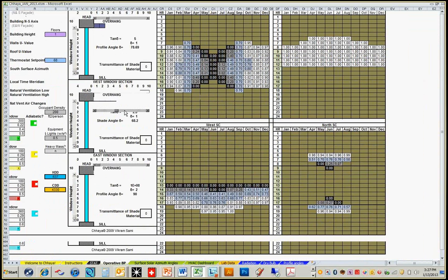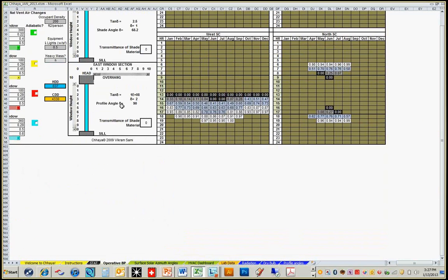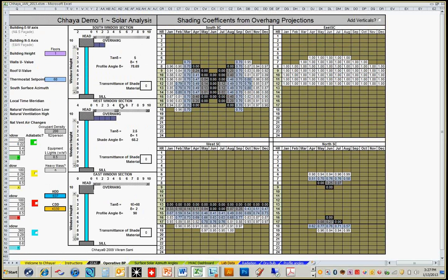And this is a really good illustration of why a west facade is a lot harder to shade than a south facade. For the same 4-foot overhang, on the south side, for pretty much most of the summer months, you're fully shaded, and then in September you're reasonably shaded.